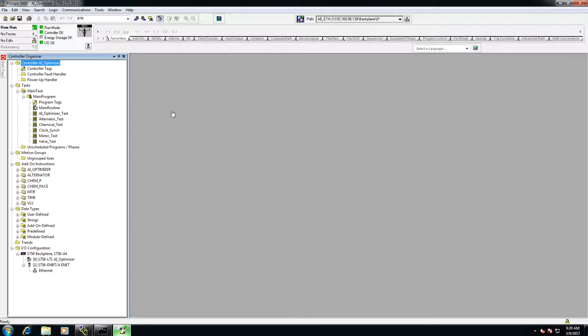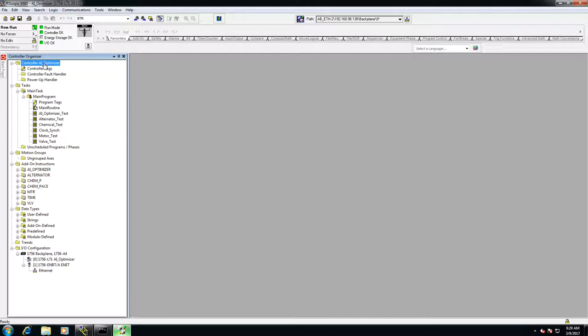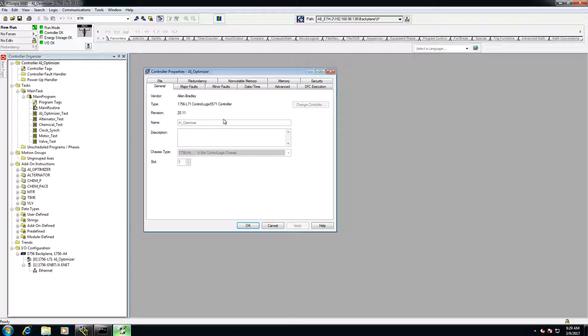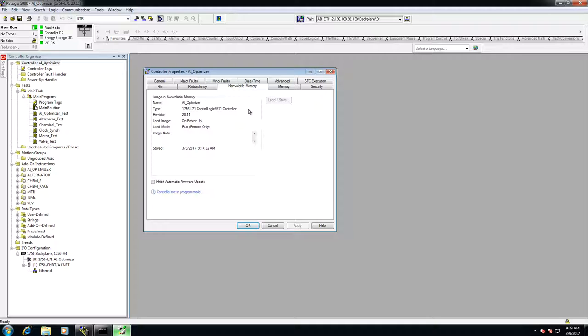So the first thing you do is you'll be here with your program online. You will go to the controller properties, and it'll come up here, and you'll go to the non-volatile memory tab. Now, to do this, you have to actually be in the program mode, so you would need to shut down any processes running on this PLC.